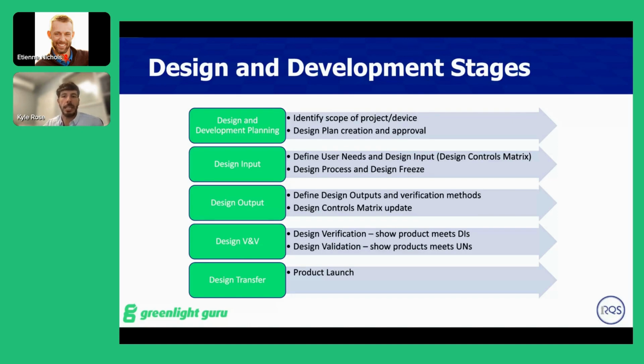Again, design review at each one of these stages to make sure you're formally having these reviewed. Design V&V activities. So this is identifying that you're testing, what you're testing, and where it'll be documented. In some cases, your verification protocols can cover multiple inputs or multiple outputs. You can have one protocol that covers multiple things. Validation is typically more inclusive of all user needs, so it is a test that covers a lot of user needs together. Once these activities are done, that's when you typically move into design transfer.